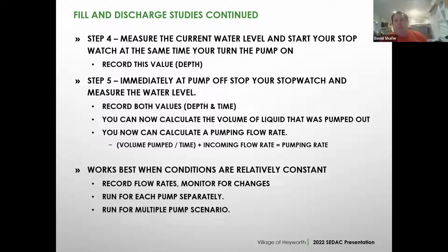This type of study works best if conditions are relatively constant. So you don't want to do it at 7 or 8 in the morning when everybody's waking up and that morning rush of wastewater is coming into your facility. You want to do it at 2 in the afternoon when the flows are relatively constant over the 10 or 15 minutes it might take. You want to run each pump separately, and then you might want to run a multiple pump scenario as well. If you do a little searching on the internet, there are some pre-made spreadsheets for pump drawdown tests or wastewater pump tests, so you don't have to do all the math yourself.